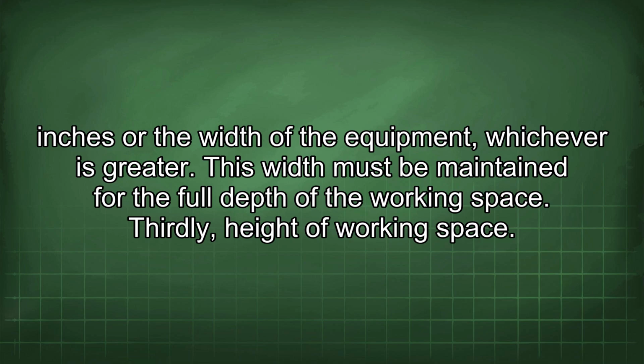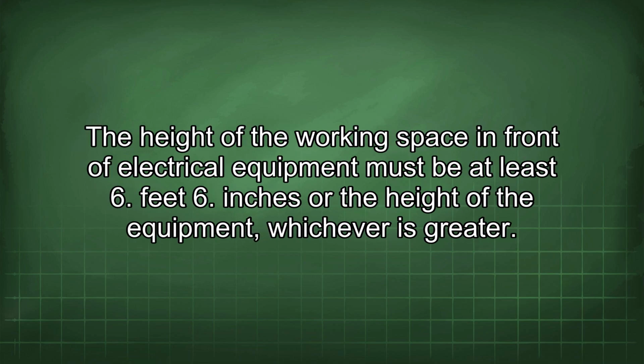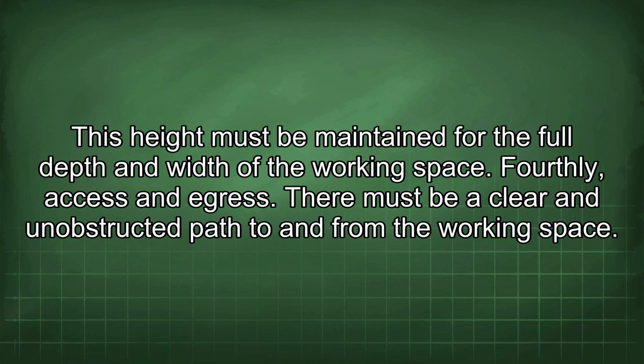Thirdly, height of working space. The height of the working space in front of electrical equipment must be at least 6 feet 6 inches or the height of the equipment, whichever is greater. This height must be maintained for the full depth and width of the working space.